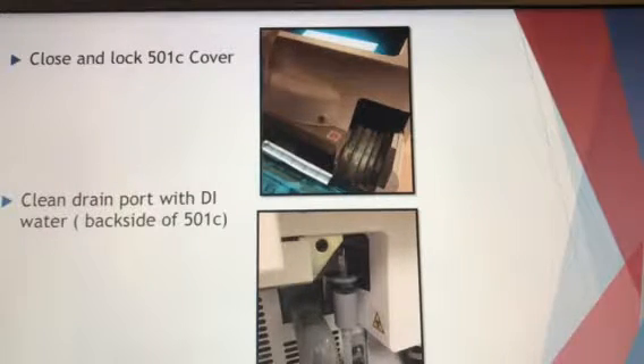If it's not tightened good enough, the machine will throw a red flag and an alarm, so it just puts in delay in what we're doing. So just make sure it's really nice and tight. Once that's done, you're going to take a cotton swab, moisten it with DI water, go ahead and walk all the way around to the back side of the 501, and there'll be a little drain port there as pictured in the second picture down there at the bottom. There's usually a little drop of water that's attached to it, and you're just going to go over that with your cotton swab. And we do this just to make sure that dab of water doesn't crystallize, so we're just making sure we're cleaning it every day. If it crystallizes, that's not good.